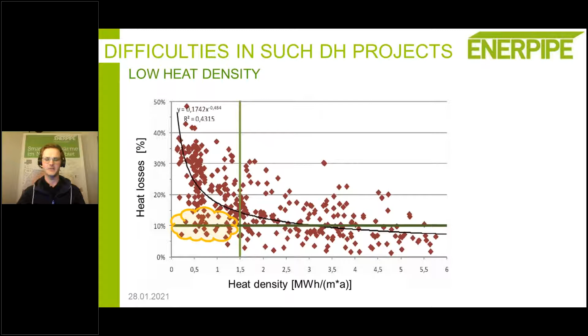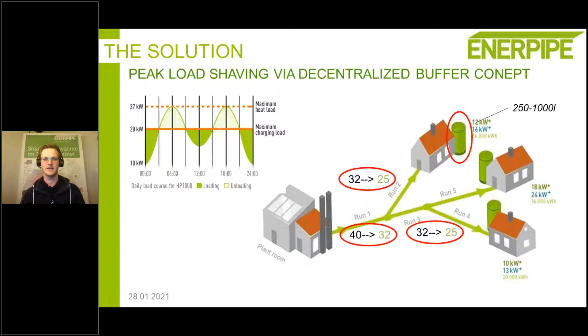So in this case, you say, okay, why a decentralized buffer tank? On the left-hand side, you can see that there is quite often a peak load in the morning, which is necessary to provide to the house because of heating and domestic hot water. If you don't have a buffer tank in the house, then you have to transport it through the pipe, and also through the plate heat exchanger. At that moment, the heat has to transfer from the district heating network to the house. But if I have a buffer tank and not just a plate heat exchanger, you can make a peak load shaving of your maximum heat load, and this helps to reduce your maximum heat load, and also to reduce the pipe sizes in the network. So perhaps before you had 40 mm pipes, now you can go to 32 mm pipes. So this really helps with the network design as well.